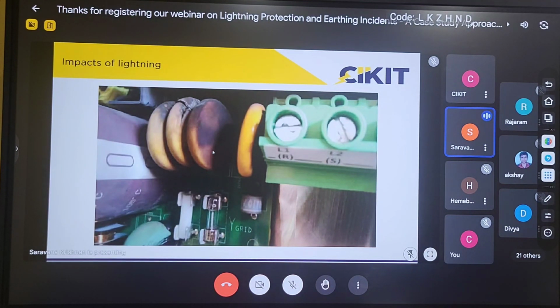Here you can closely observe that the fuse has not blown. If the purpose of a fuse is to protect the electronic equipment, then in the case of surges the fuse might have blown, but here the fuse is not blown and the component got damaged. From this we came to understand that the damage is caused not by the power frequency supply, but mainly by the surges coming through this line. If surges approach, the fuses or MCBs which we are providing won't operate, so the equipment cannot be protected by the fuse, MCB or stabilizers which we are using, because their sensitivity is not that high.